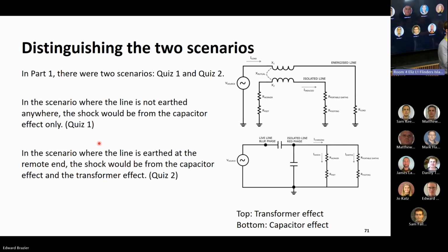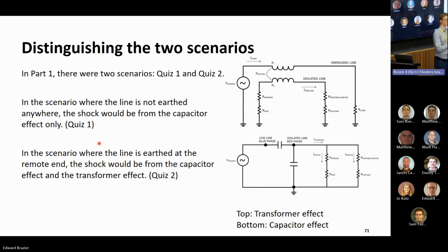To clear up any confusion between the two scenarios: in quiz 1, when the worker touched the line, there were no earths on the isolated line, so it was just a capacitor effect. In quiz 2, when the worker touches the line, there are just the remote earths a few kilometres away, and in that case we've got both the capacitor effect and the transformer effect contributing to the shock current.